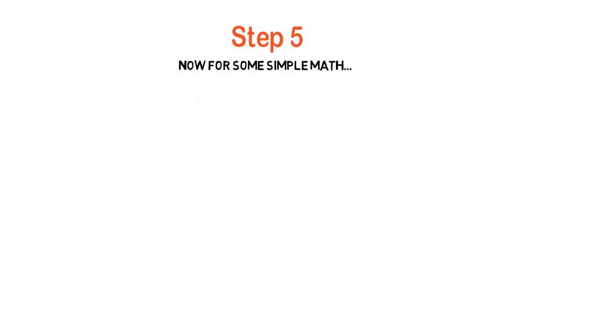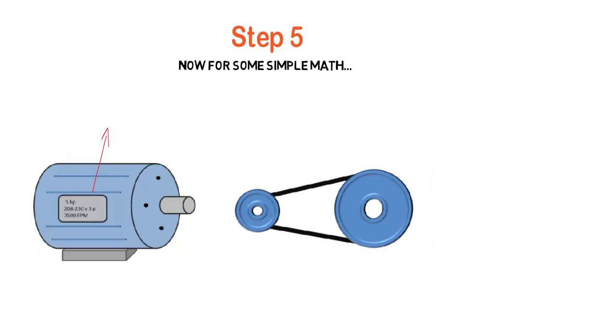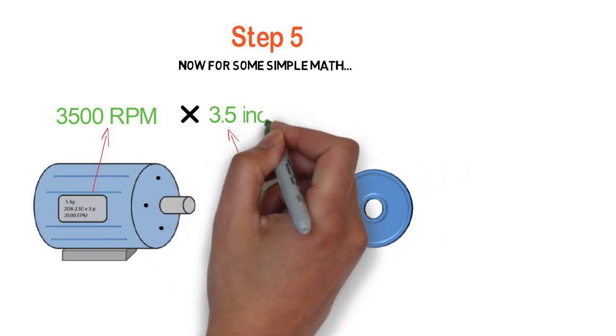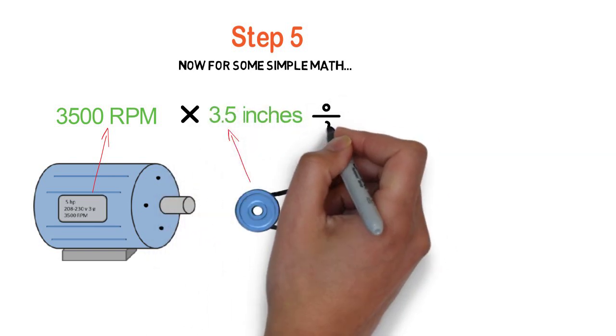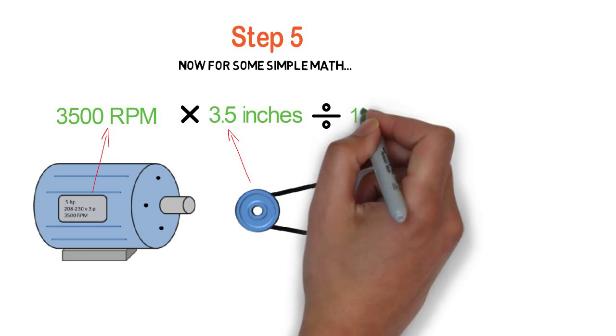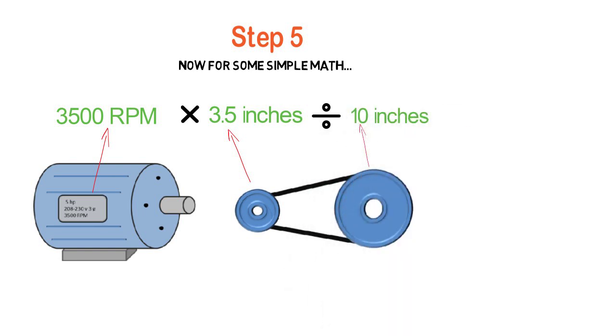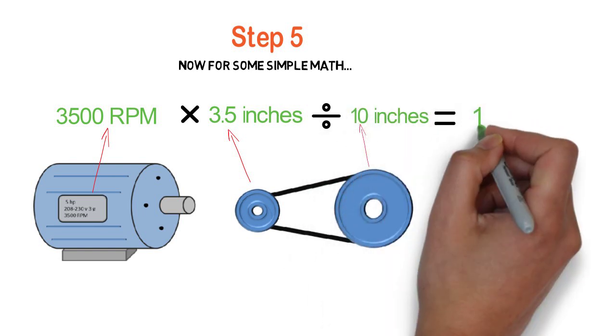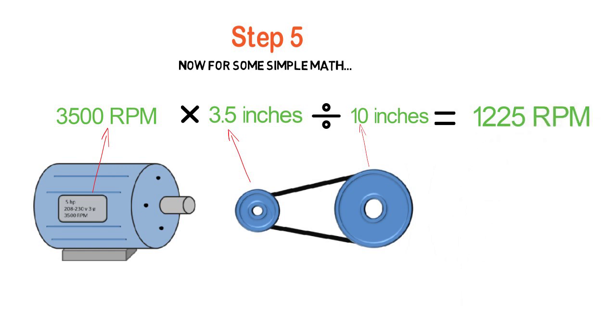Step five, we're going to do some simple math. We're going to take motor RPM, which in our case was 3,500. We're going to multiply it times the functional diameter of the motor shiv, which was three and a half inches. And then we're going to divide that by the blower shiv, which in our case was 10 inches. That gives us 1,225 blower RPM. Told you it was simple.